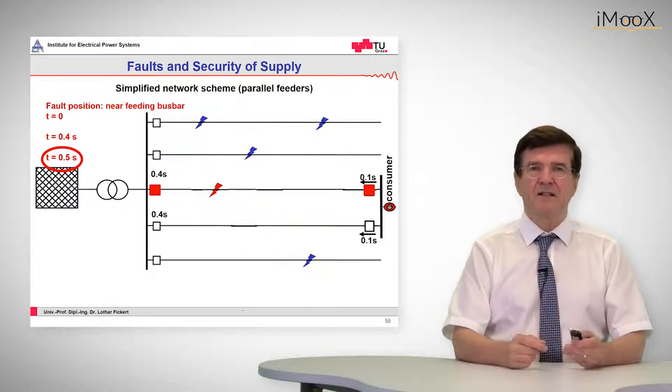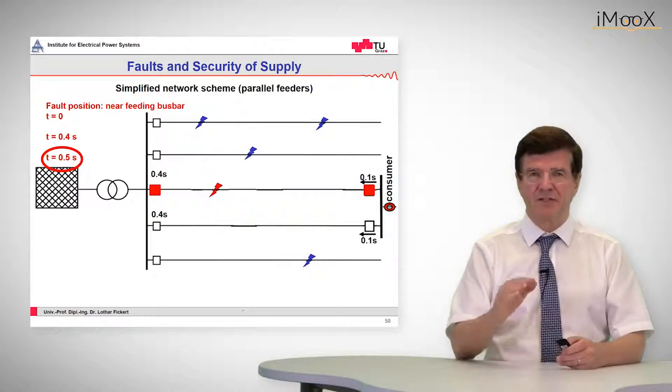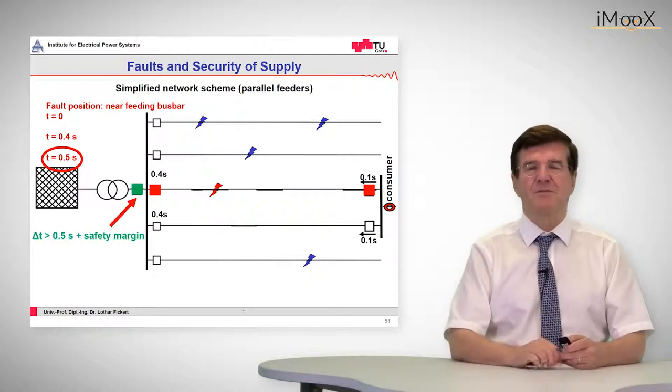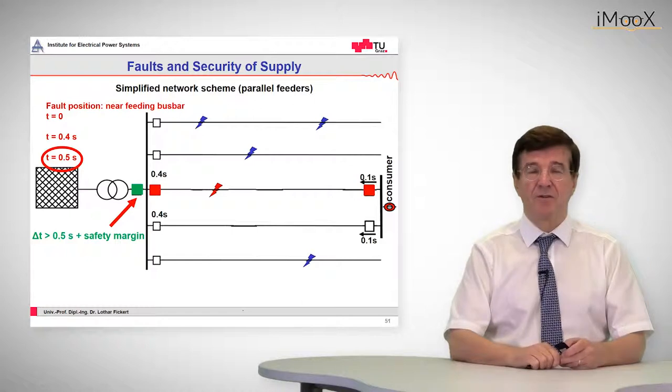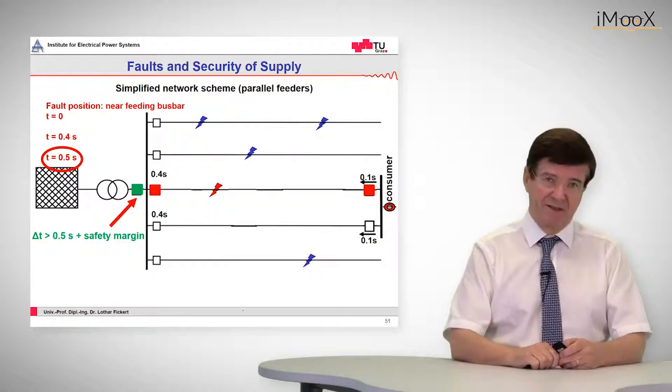So this may look as a small increase in tripping time, but when it comes to the backup function, we must take care that also the backup function will take of this possible situation. So that means the basic tripping time is not given by 0.4 seconds, but 0.5 seconds, plus the grading margin, as was indicated before.